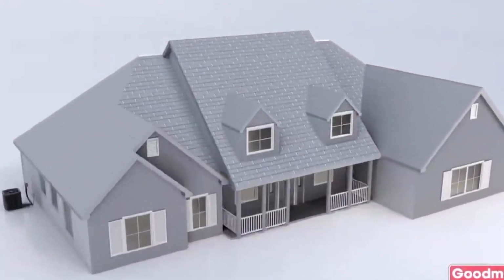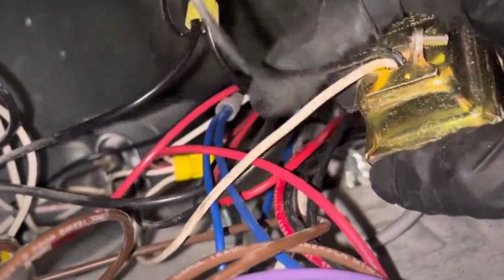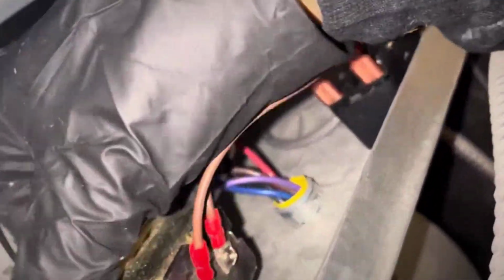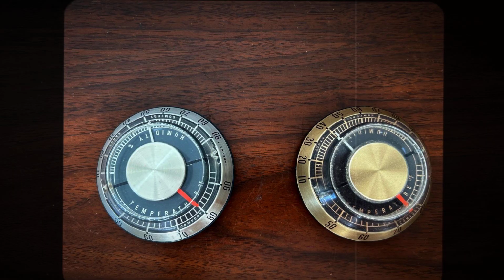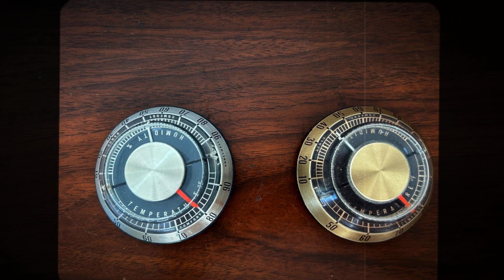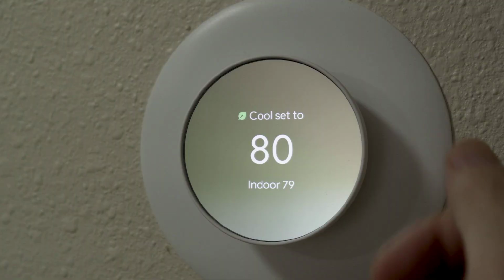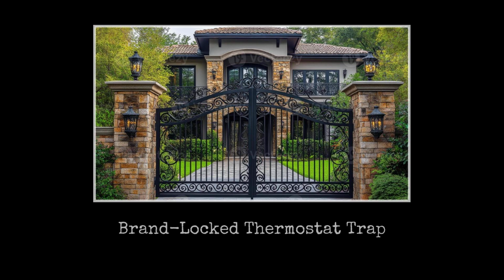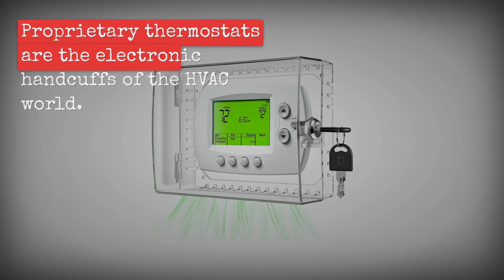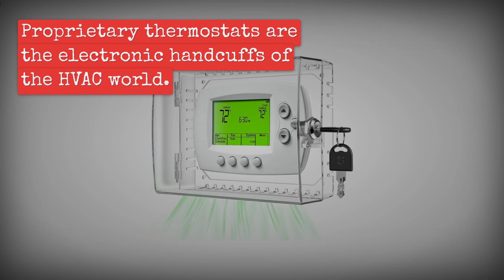Here is the secret: almost every residential HVAC system in America runs on 24-volt AC control signals. That has been the standard since the 1950s. When a contractor says you need their proprietary thermostat, what they're really saying is we want to lock you into our ecosystem so you can never use anyone else's equipment. Proprietary thermostats are the electronic handcuffs of the HVAC world.